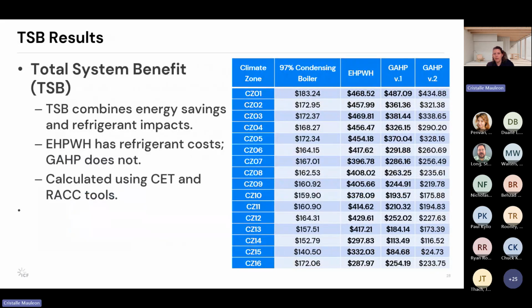This slide shows the total system benefit for each system across the selected climate zones. The TSB accounts for energy savings as well as refrigerant impacts, calculated using the CEDARS cost effectiveness tool, or CET, and the refrigerant avoided cost calculator 3.0, that would be RACC. The electric heat pump water heater includes some refrigerant costs because it uses refrigerants that have environmental impacts. The GAHP uses a refrigerant with zero GWP because it's ammonia, so its refrigerant costs are excluded. As shown in the table, the GAHP version 1 and electric heat pump water heater generally offer the highest TSB values, especially in cooler zones.